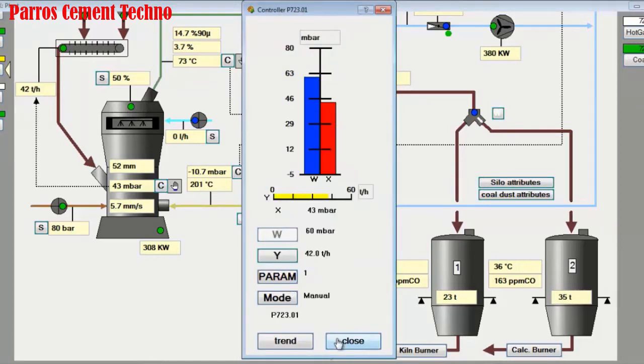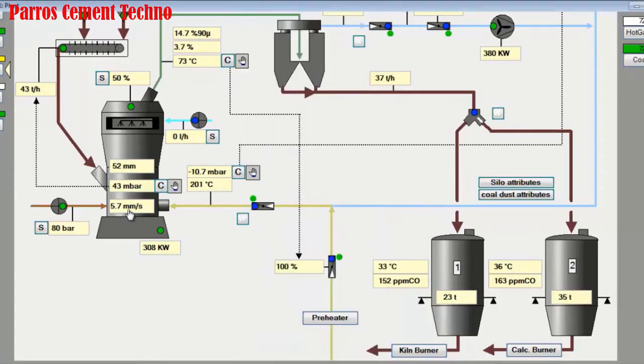Mill vibration is kept below 4 millimeters per second. We increase again by 1 ton of mill feed so that the vibration is lower than 4 millimeters per second.